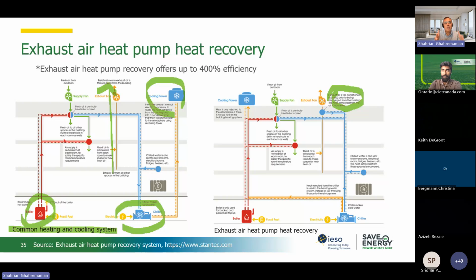Yeah, I mean, the idea is that we cannot install a plate heat exchanger. We cannot install a wheel, energy or heat recovery wheel for the exhaust fan. We are not allowed to do that. But we can install some kind of a heat recovery chiller, or an air conditioning system, which is basically taking advantage of the heat. So this is the heat pump that takes the heat from the exhaust air and converts it to cooling for us and sends it to the cooling system that you have. So in your application, if you have simultaneous need of cooling and heating, then you might consider this one. If not, during the heating season you need heating, so then you can consider heat pumps that take the heat and pump that heat back to you.